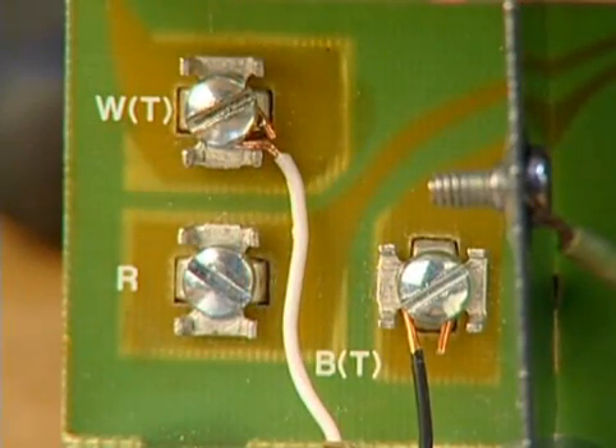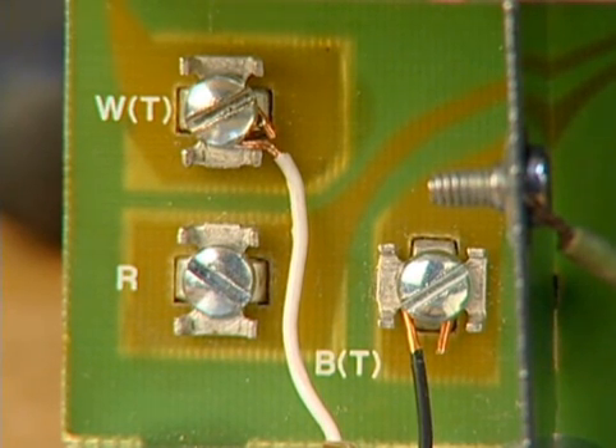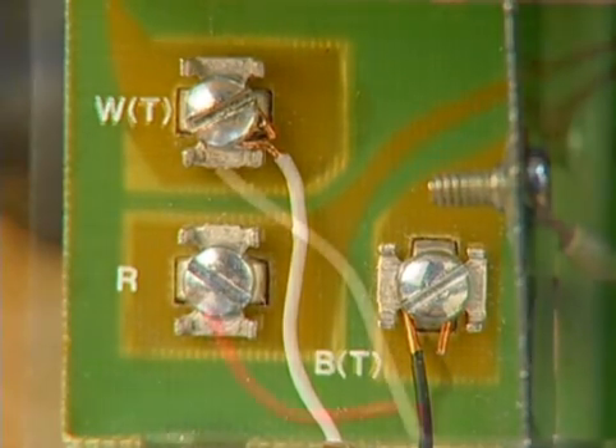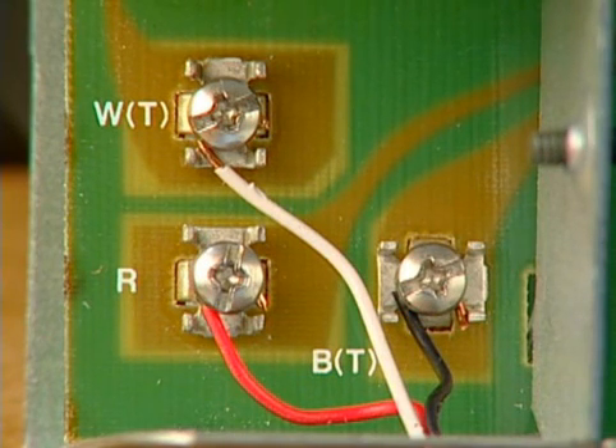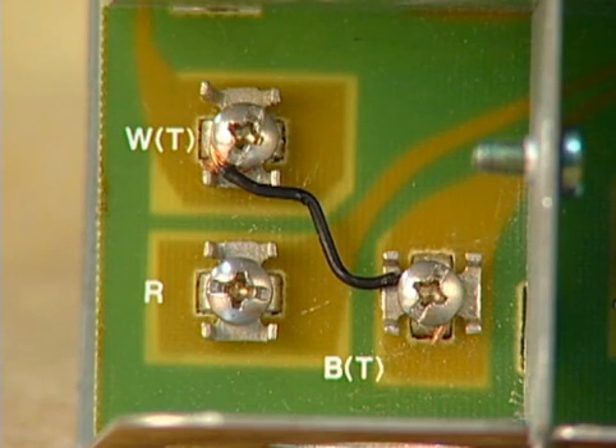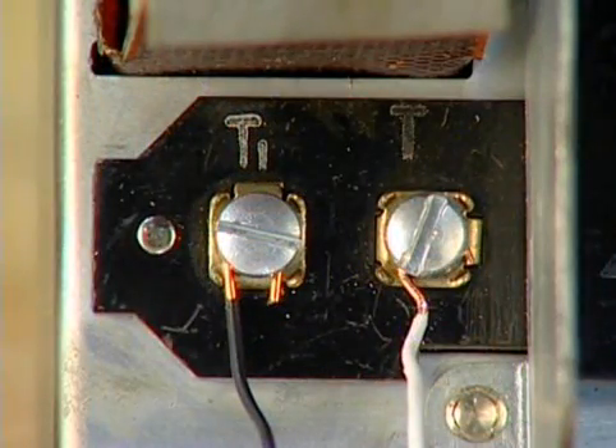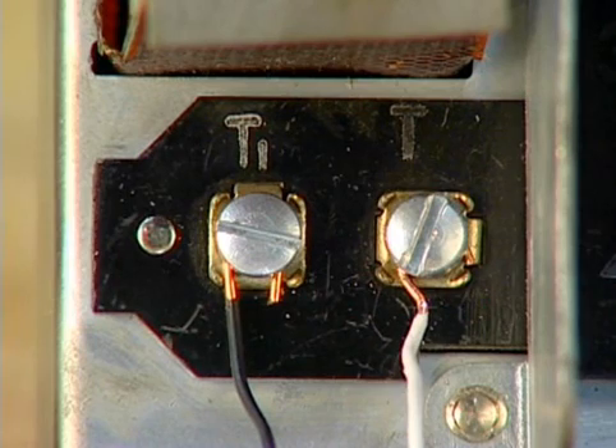The low voltage side of this primary control has 3 terminals, R, W, and B. If the system has a 2-wire thermostat, it is connected to the W and B terminals. If a 3-wire heat-only thermostat is used, connect the red wire to terminal R, white wire to W, and black wire to B. If there are no low-voltage devices connected to the primary control, a jumper is placed between the W and B terminals. Some models only have 2 low-voltage terminals for the thermostat connection, normally labeled TT.